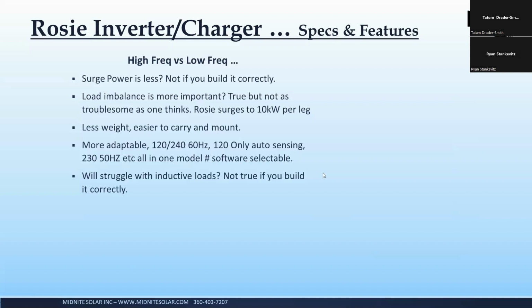That's much easier on our backs. We talked about the voltage being selectable in software. That's another feature of high frequency. You can't do that with the transformer based inverter. And then the other one that I hear a lot is that high frequency will struggle with inductive loads. And that, again, kind of goes right along with number one, the surge power. And if it's built correctly, it will not struggle.